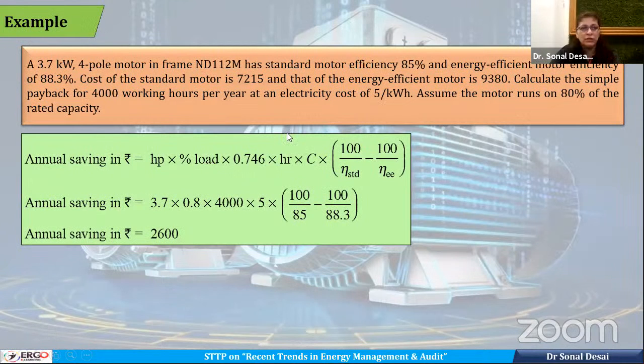There is a good example given: a 3.7 kilowatt 4-pole motor in the given frame has a standard efficiency of 85% and the energy efficient motor is 88.3%. The cost of the standard motor is 7,215 rupees, while the energy efficient motor is 9,380 rupees. Calculate the simple payback for 4,000 working hours at the cost of 5 rupees per unit, assuming the motor runs at 80% of the load.